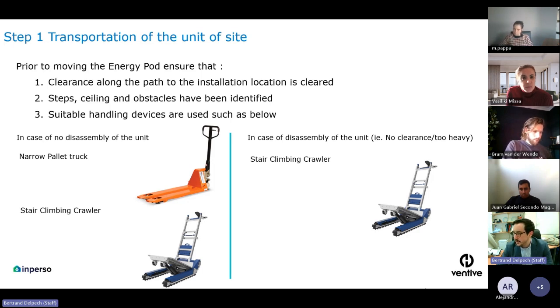So here, for example, if you don't need to disassemble your unit and you're installing on the ground floor, a pallet truck is more than sufficient to move the system, with at least 3 people to make sure that it doesn't tip. It's very important during movement, it could tip, but just to be safe, do not handle it on your own.